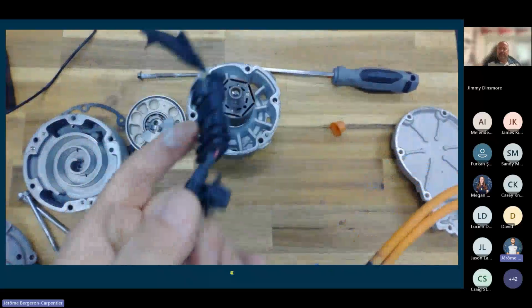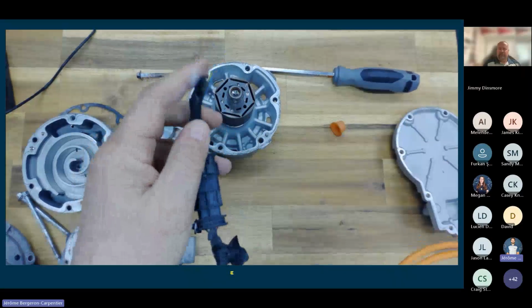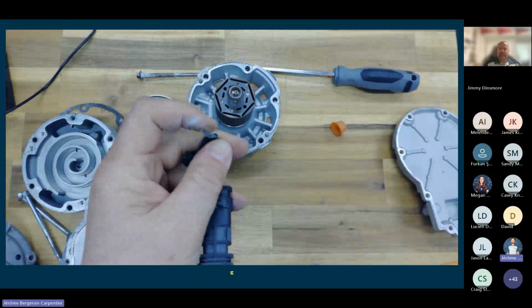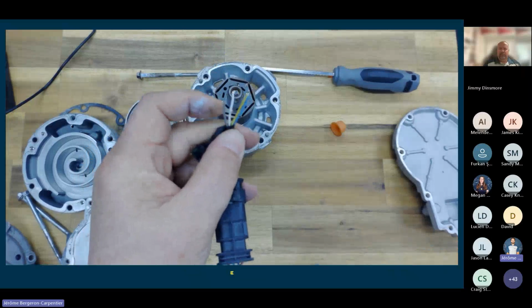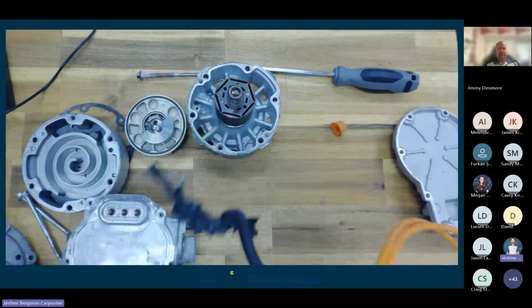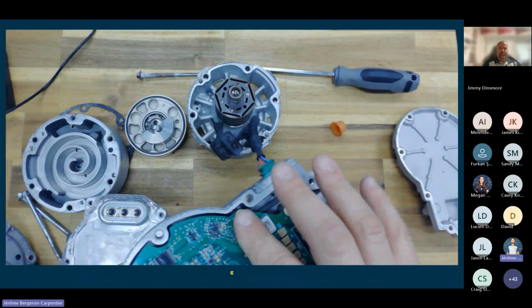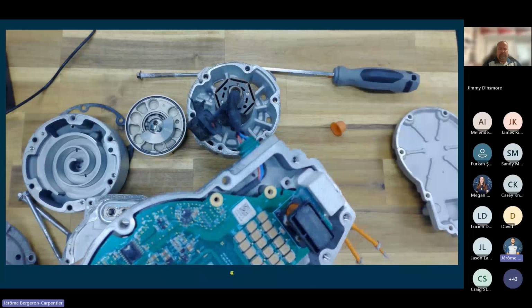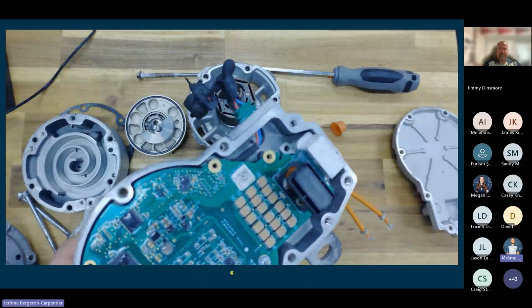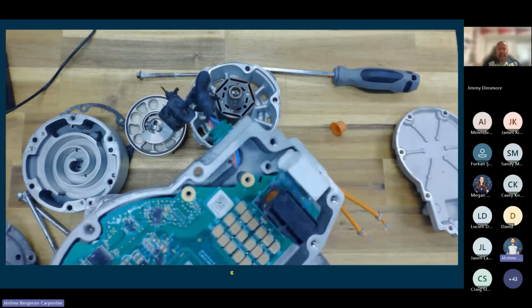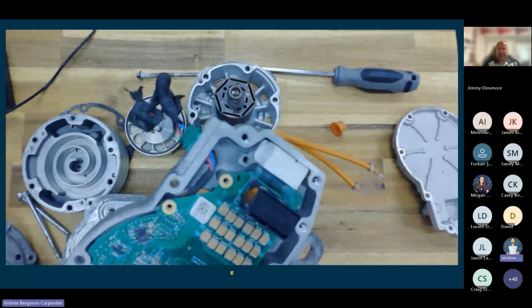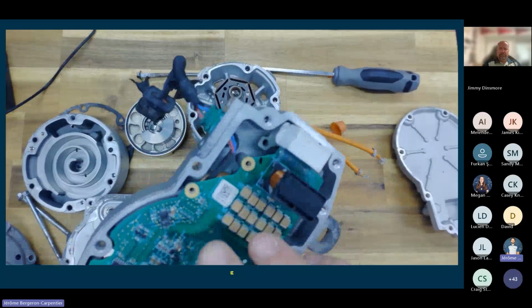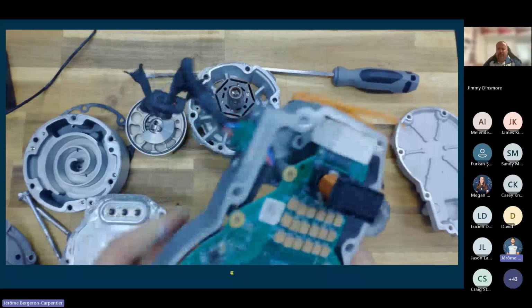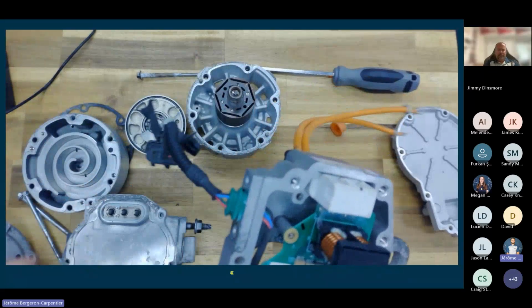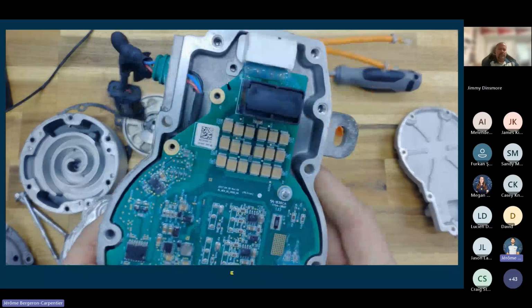So the other thing is too, the compressor communication is done through CAN bus. So most compressors are like this. So we see our high and low CAN wires there, our blue and our yellow wire. And of course we have our positive and our ground. And the communication that the board will give us is mostly temperature, RPM, pressure in some cases, so it gives me those pieces of information, as well as diagnostics. So I can get diagnostics through the scan tool onboard computer to actually do that.